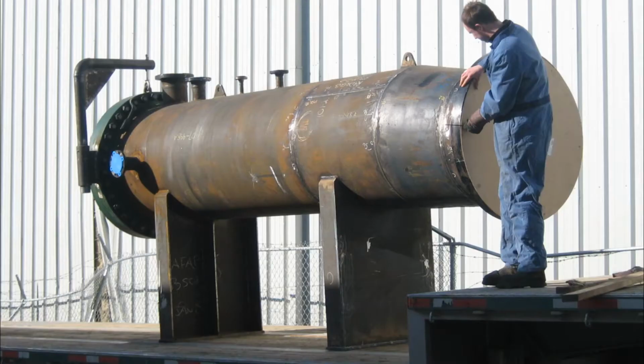Bismillah ir-Rahman ir-Rahim. The tank of an oil-filled distribution transformer is not designed, manufactured or operated to be a pressurized vessel. What does this mean? We need to understand what is meant by a pressurized vessel. A pressurized vessel means there is a container where the pressure inside is much higher than the pressure outside. So it will have a special design and manufacture to be able to withstand this difference in pressure.